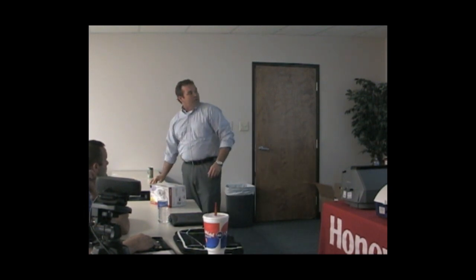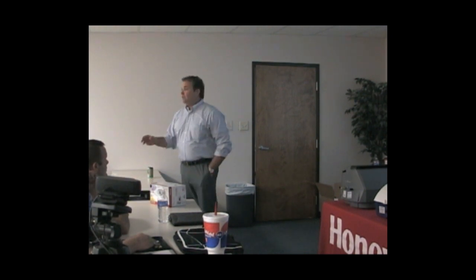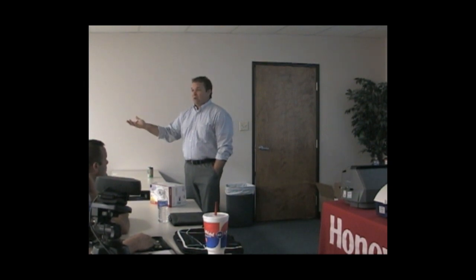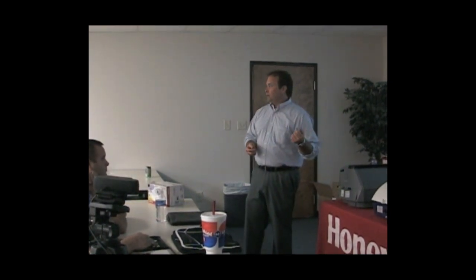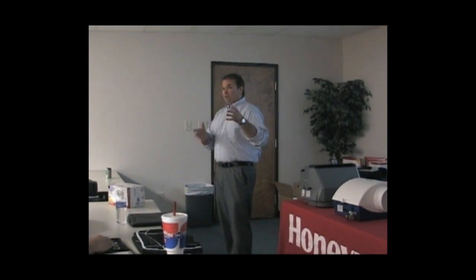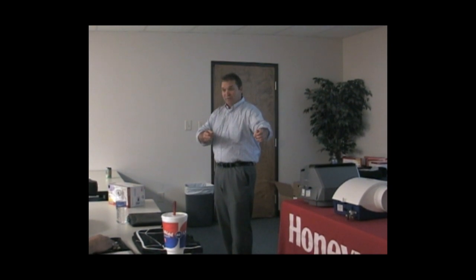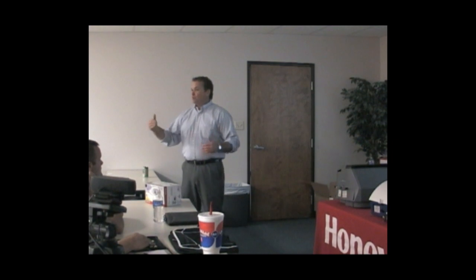On geothermal, though, some customers don't need third stage to cut on until it's almost 0 outside, right? And that's been a big problem with geo jobs. So we added this feature for you guys on geo, where instead of not installing the backup electric, or they've got the breaker shut off, and now they've got no backup until they call somebody to install the kit or turn the breaker back on—I can spread this out, my second, third stage, from 2 to 15 degrees. So now I've got a proper backup on that window. I don't have that customer calling me telling me, hey, you just sold me a $20,000 geothermal system and my electric bill is still $400. The reason is because those strips are cutting on too fast. So you can totally spread that out with this thermostat.